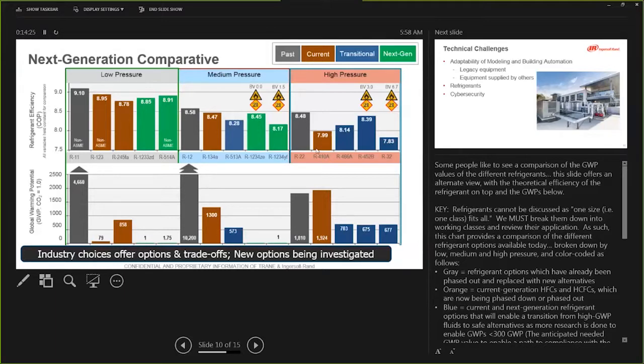There are a few what I would call transitional options for 410A, which do lower the global warming potential. And you see we have 3 of them listed here. Our 466A, which was just announced very recently by Honeywell. We're in technology development on that today. It's a non-flammable refrigerant and has a global warming potential about 40% that of 410A. So it's transitional because it won't meet our long-term needs for global warming potential. Similarly, our 452B, which is design compatible with 410A, it's an almost exact drop into 410A, so it can be used very, very quickly in the industry on existing equipment if necessary. Also has about 40% of the global warming potential.